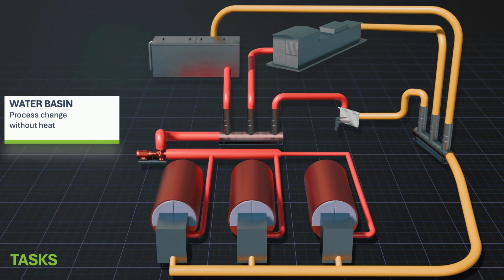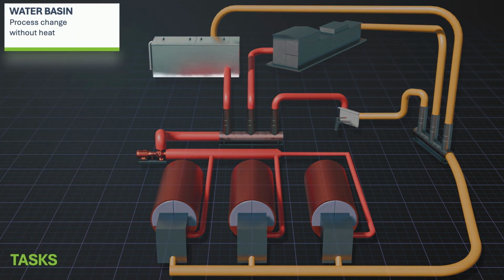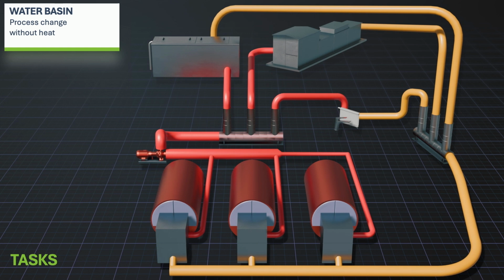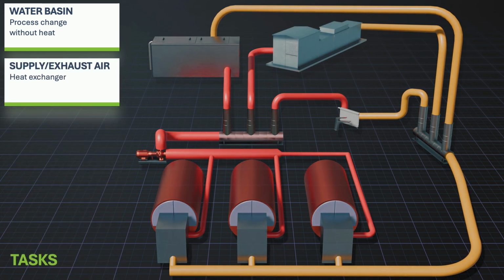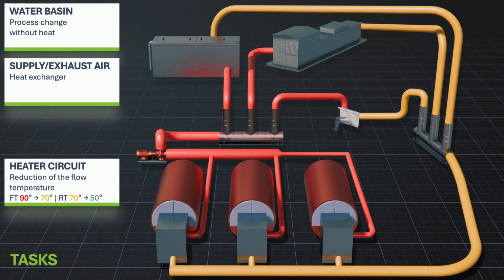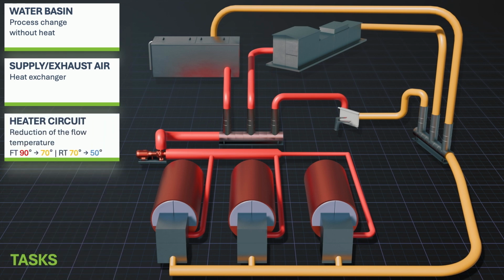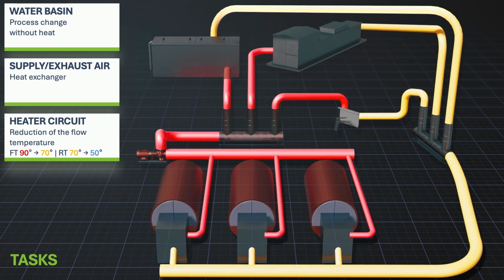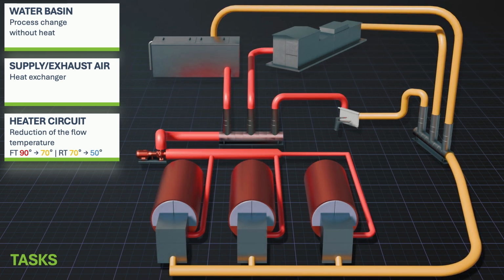The hot water basin of the paint shop can then be dispensed with in the future, as the new energy-optimized engineering process will manage without heat. New heat exchangers can be installed in the ventilation systems so that the cold air supply is preheated with the warm exhaust. After the test, the flow and return temperature in the entire heating network can be reduced by 20 degrees Kelvin. This leads to a significant reduction in heat losses.